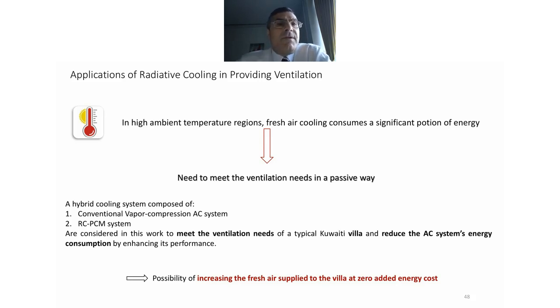Basically, we have high outdoor temperatures. We want to bring fresh air from outside into the house to clean out contaminations and keep a healthy environment for people inside. However, this ventilation air needs to be cooled down. Outside temperature in the summertime, for example, is about 48 degrees C. If we bring it inside, we have to cool it down all the way to 24 degrees C. This is a huge cooling load, and the ventilation load usually varies depending on the weather, but it may reach 35% of the total cooling load.